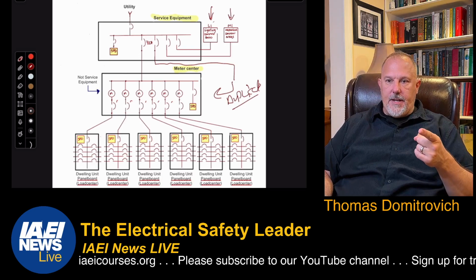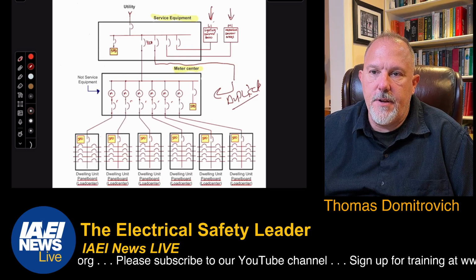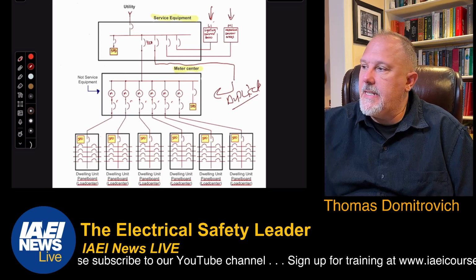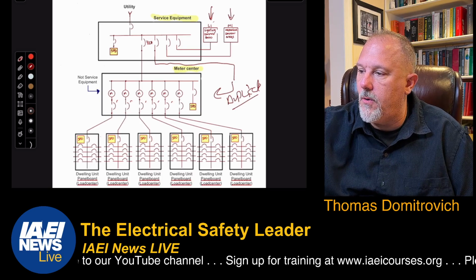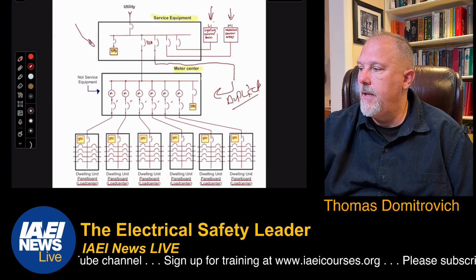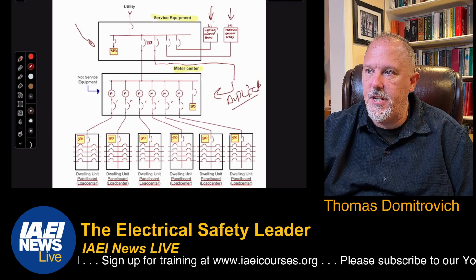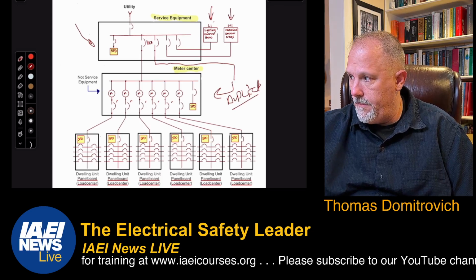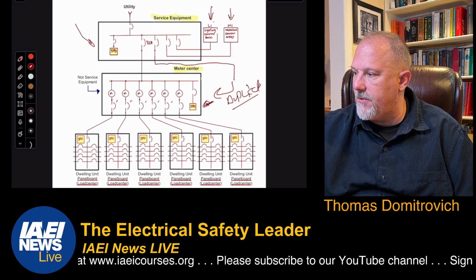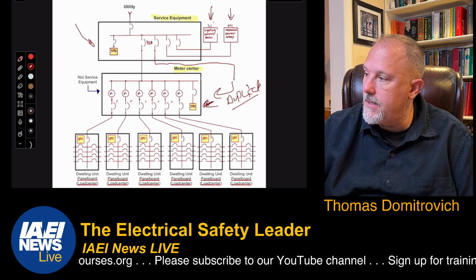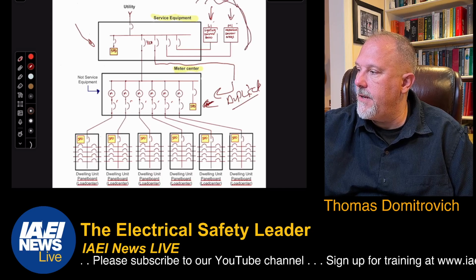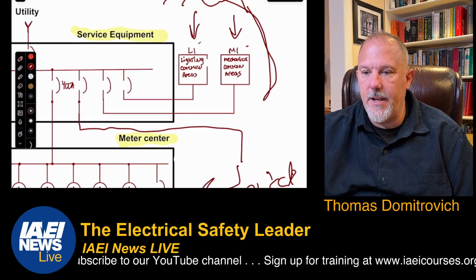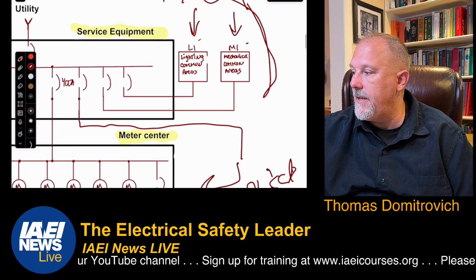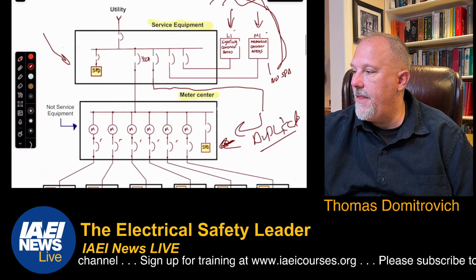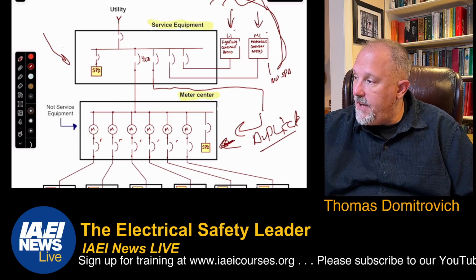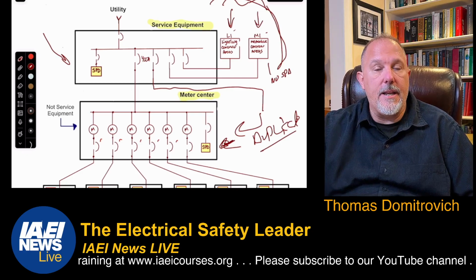And now I have to apply Article 215 and 230. So let's talk about 230 first. 230 says service equipment has to have an SPD, and lo and behold, I've got an SPD there. And it says I do not need an SPD there if I have it at each next level distribution equipment downstream towards the load. Well, I have it at each of these meter centers. Every meter center has an SPD, except these two panels over here. Those two panels, lighting, common areas, and mechanical, do not have an SPD. No SPD. Well, then I can't meet the exception unless I put an SPD at those panels. If I put SPD there, then I would not need it in the service equipment.